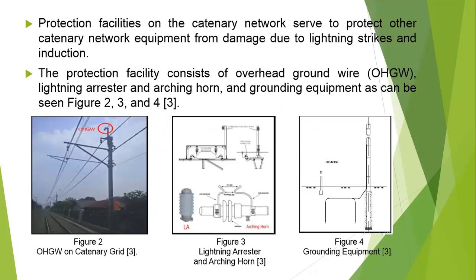Protection facilities on the catenary network serve to protect other catenary network equipment from damage due to lightning strikes and induction. The protection facility consists of overhead ground wire OHGW, lightning arrestor and arcing horn, and grounding equipment, as can be seen in figures 2, 3, and 4.